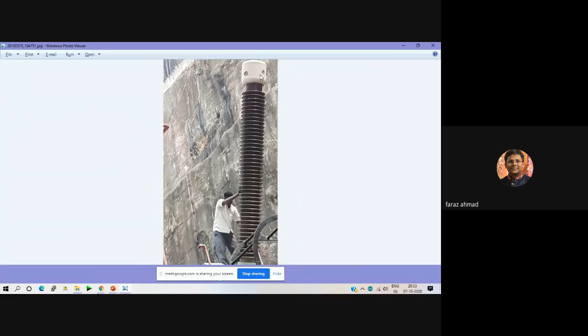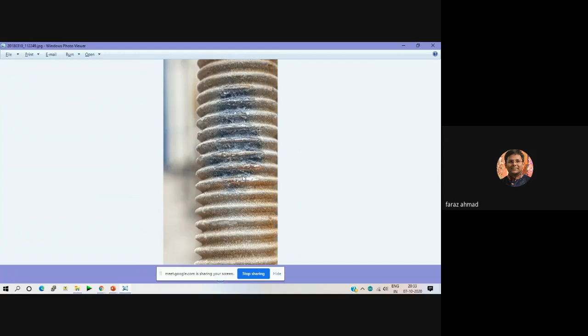This is installed at the top of the generating transformer, and it is at a very high point. The height is too much, but still because of this you could hear the sparks from around over 100 to 200 meters. And this is a normal M12 bolt, meaning the diameter of this is 12 mm - so this is a normal household bolt that is being used.